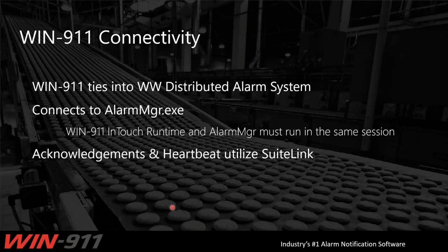And then you run our InTouch Runtime from the Start menu, which runs as an application, and it also spawns in session 1. So if you're ever in a situation where you're maybe receiving alarms but not able to acknowledge, or maybe just not receiving alarms, then you might want to double check that alarm MGR to make sure that there is one running in session 1, and then the Win911 InTouch is also running in session 1. And I'll show you more of that in our demo later.